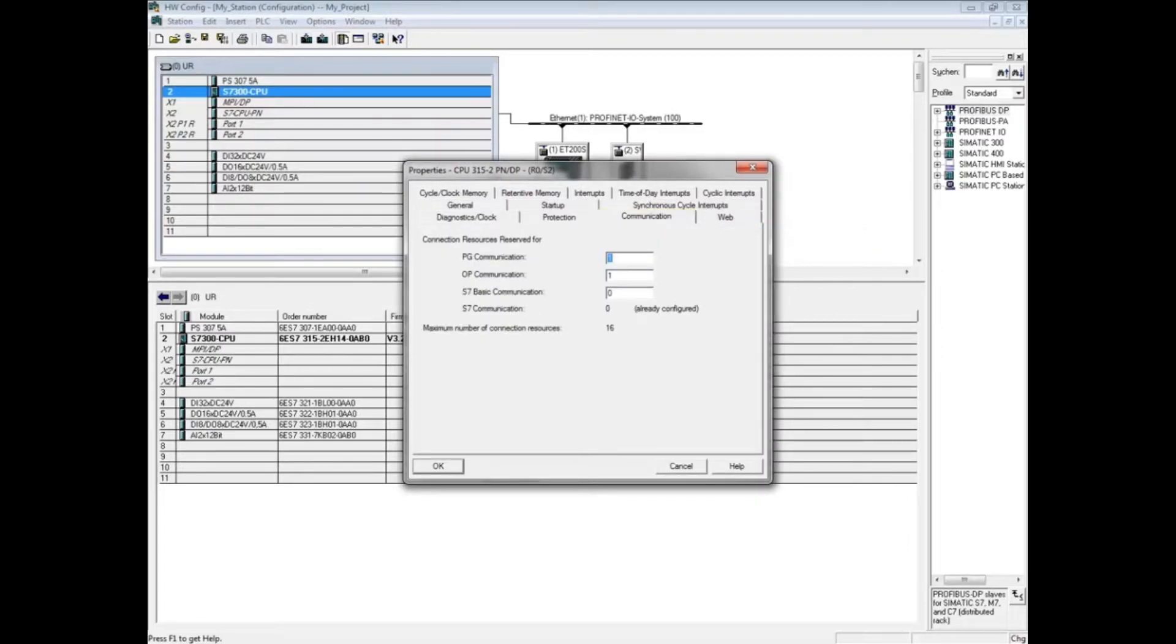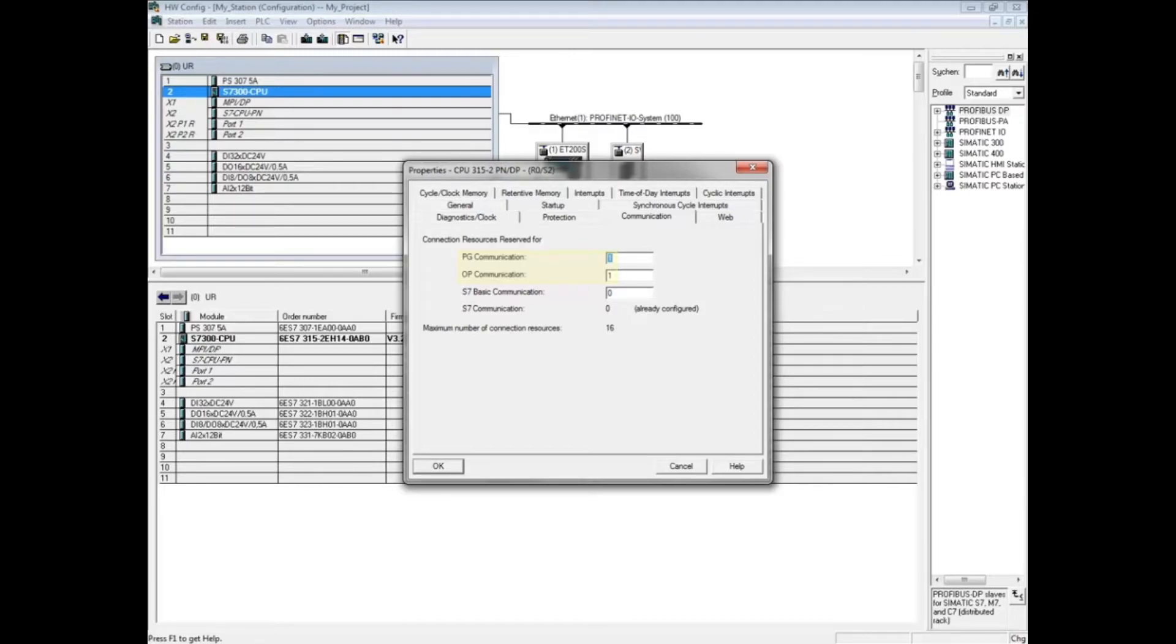This is a place where you can reserve communication resources. By default there are 16 available connections. One connection is reserved for a computer or PG and one is reserved for an HMI Operator Panel or OP.